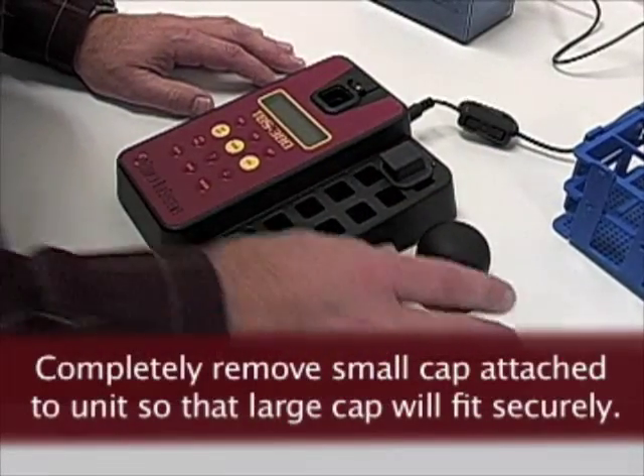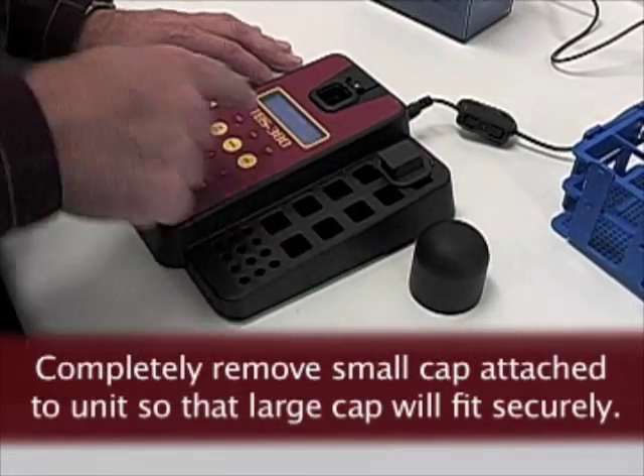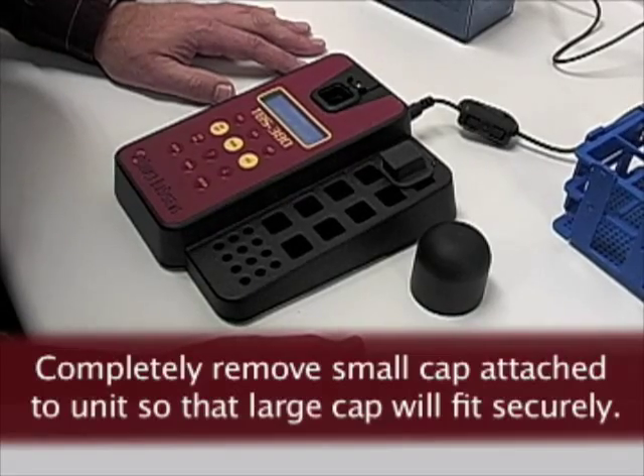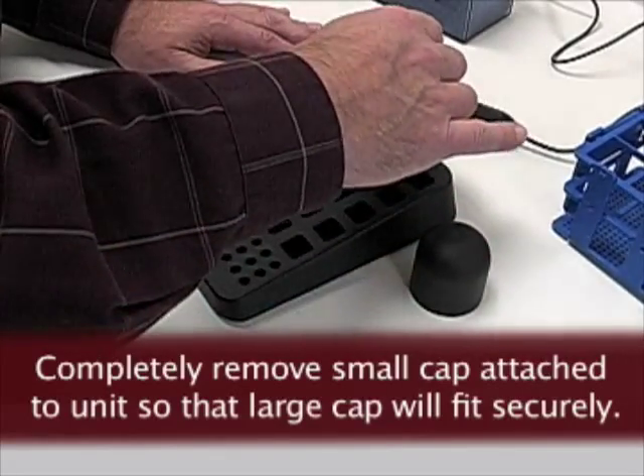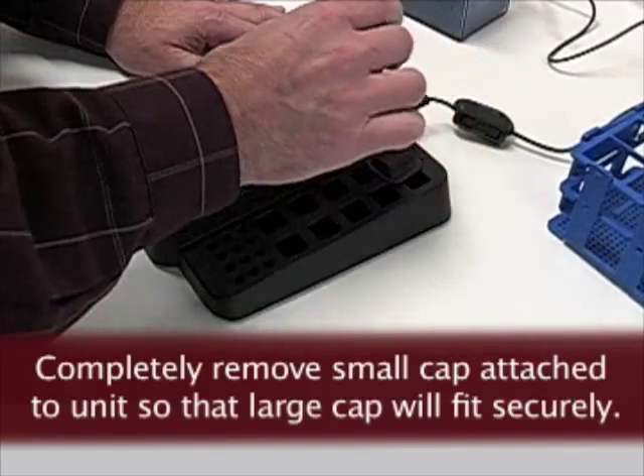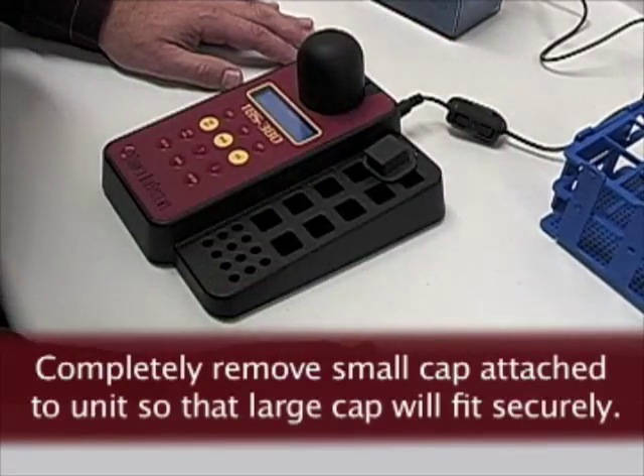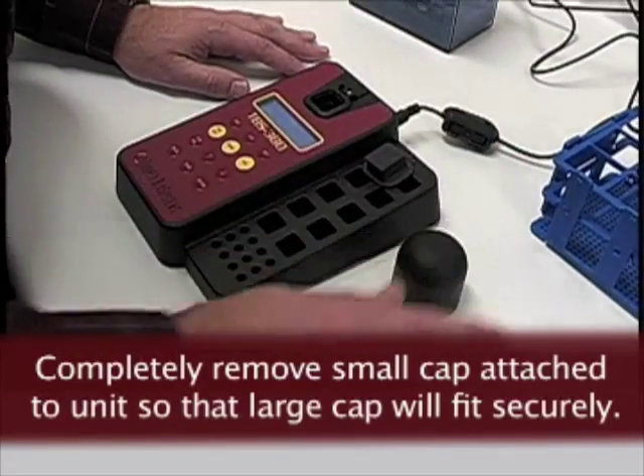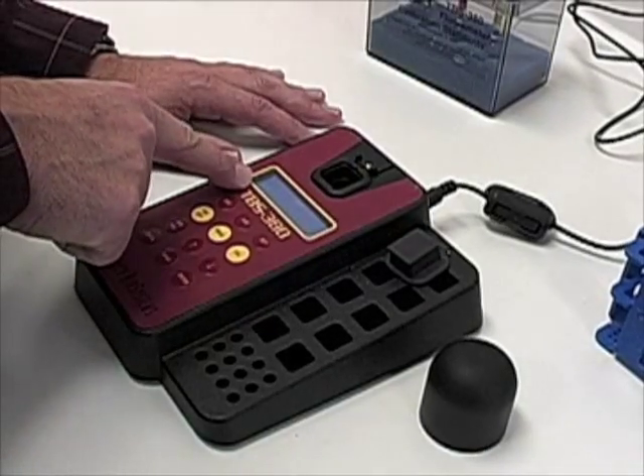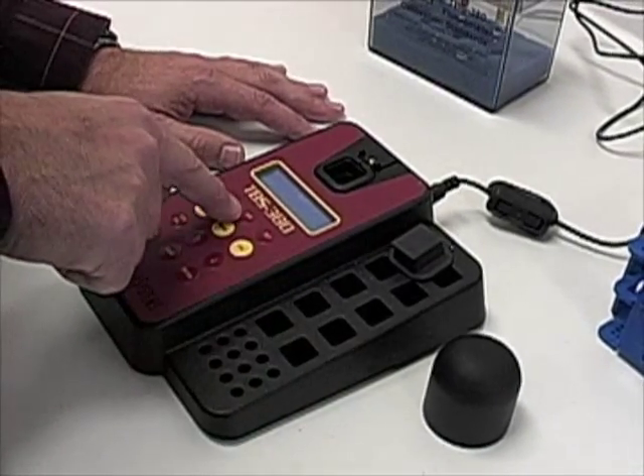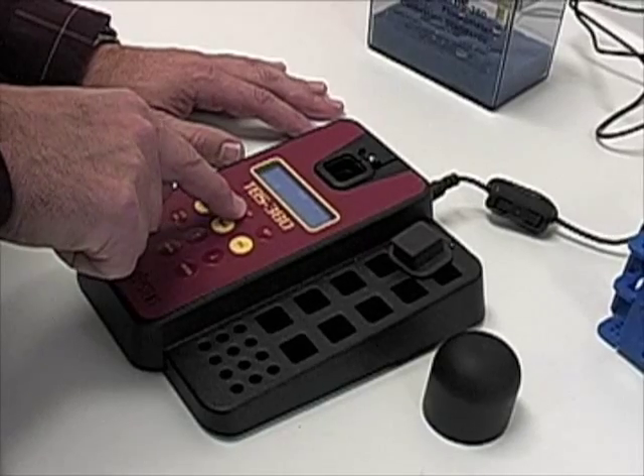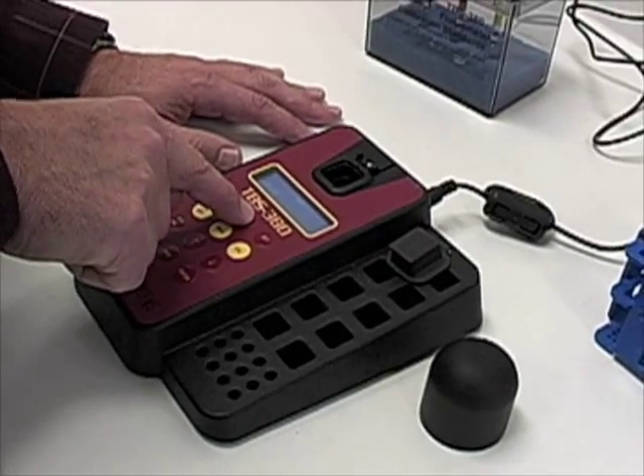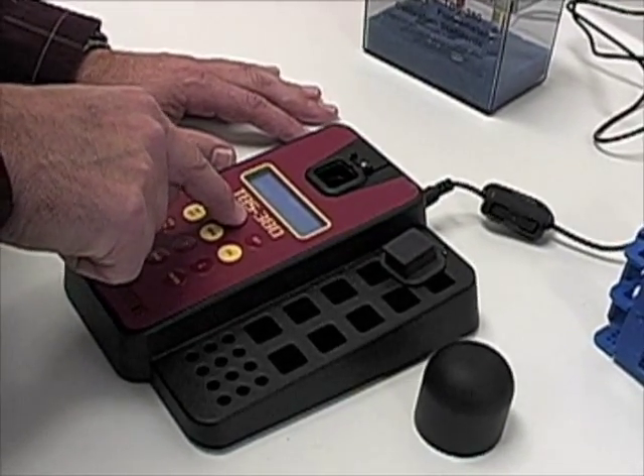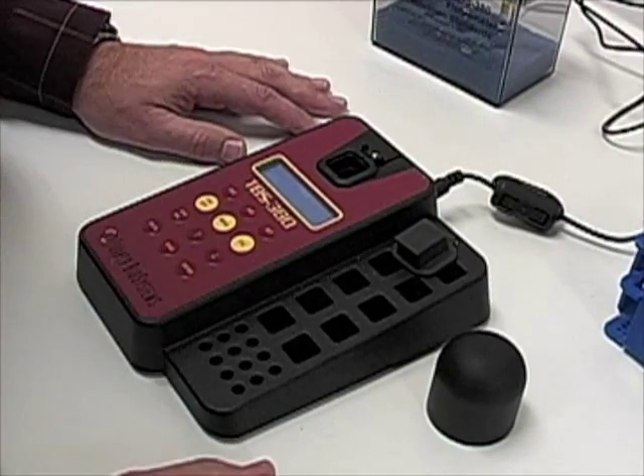To prepare the instrument, turn the power on. If you notice, I've taken off the cover so that the cap can make a nice tight seal to the instrument. Make sure that the left hand side says UV. If not, you hit this AB button, and that corresponds to blue and UV. You can go back and forth, make sure it's on UV.